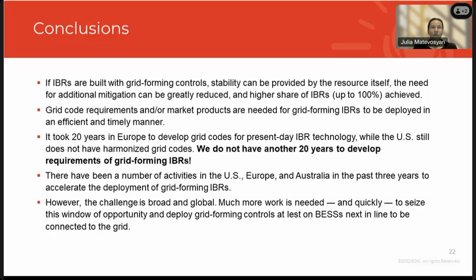And then for both solar and wind, you need to weigh revenue loss versus what you are getting for provision of grid forming capability. Whereas again, in a battery, it's already there, and it's only a short-term story. So you may say, okay, she's saying the battery is not losing revenue because it's using energy for grid forming capability, but we are just talking milliseconds during the subtransient, transient time frame when this energy is needed, but it needs to be there. Yeah, thanks.